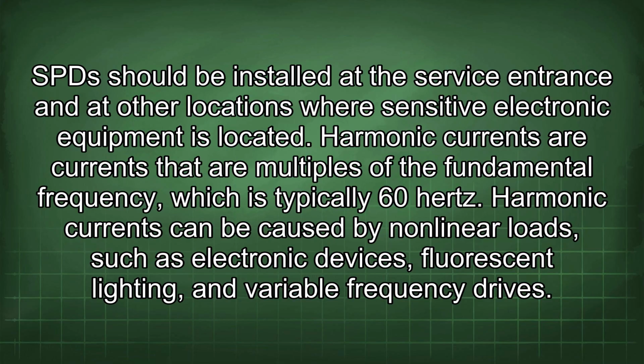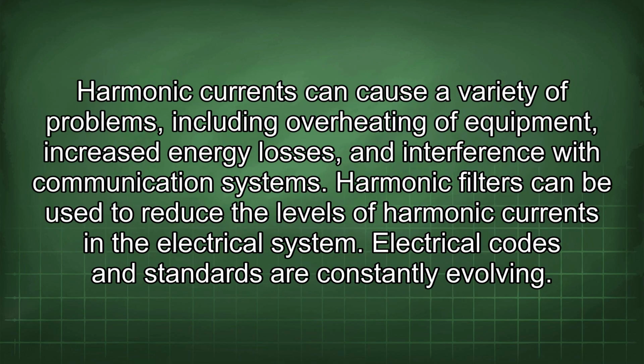Harmonic currents are currents that are multiples of the fundamental frequency, which is typically 60 Hz. Harmonic currents can be caused by nonlinear loads, such as electronic devices, fluorescent lighting, and variable frequency drives. Harmonic currents can cause a variety of problems, including overheating of equipment, increased energy losses, and interference with communication systems. Harmonic filters can be used to reduce the levels of harmonic currents in the electrical system.